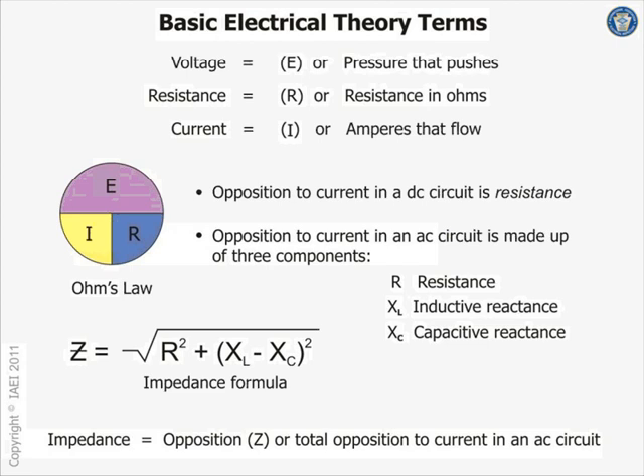Same thing, take your EMT conduit with 4 conductors, number 12 THHN in it. They're energized at 277 to ground, right? Now, if you look at the wire, your conduit is grounded, right? EMT conduit is grounded. And you put inside the conduit a wire that's hot, right? So here's a 0 level, and here's a hot conductor at 277. And in between them is air and the insulation of the conductor. Isn't that the definition of a capacitor?